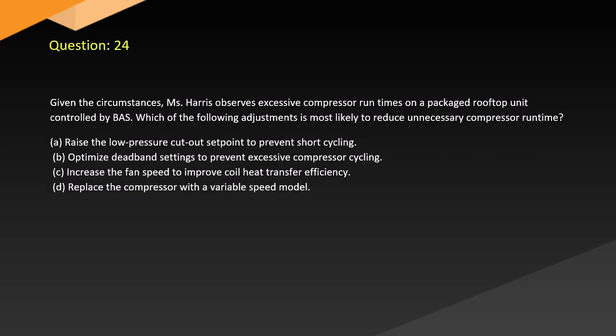Question 24. Given the circumstances, Harris observes excessive compressor run times on a packaged rooftop unit controlled by BAS. Which of the following adjustments is most likely to reduce unnecessary compressor runtime? A. Raise the low pressure cutout set point to prevent short cycling. B. Optimize deadband settings to prevent excessive compressor cycling. C. Increase the fan speed to improve coil heat transfer efficiency. D. Replace the compressor with a variable speed model.